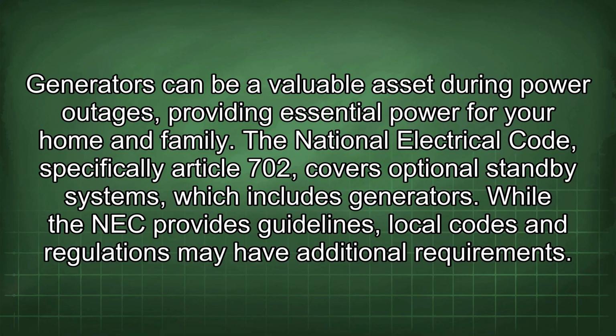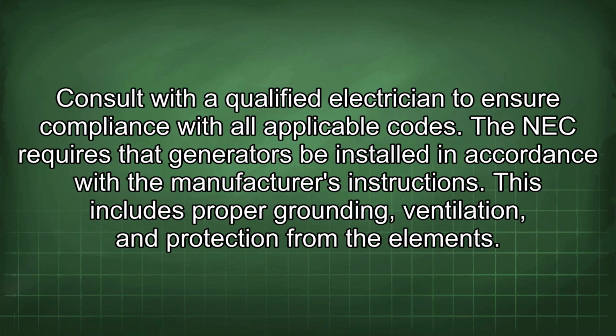The National Electrical Code, specifically Article 702, covers optional standby systems, which includes generators. While the NEC provides guidelines, local codes and regulations may have additional requirements. Consult with a qualified electrician to ensure compliance with all applicable codes. The NEC requires that generators be installed in accordance with the manufacturer's instructions. This includes proper grounding, ventilation, and protection from the elements.